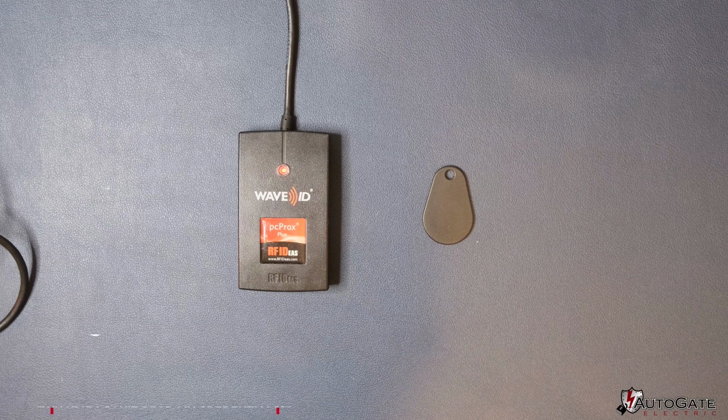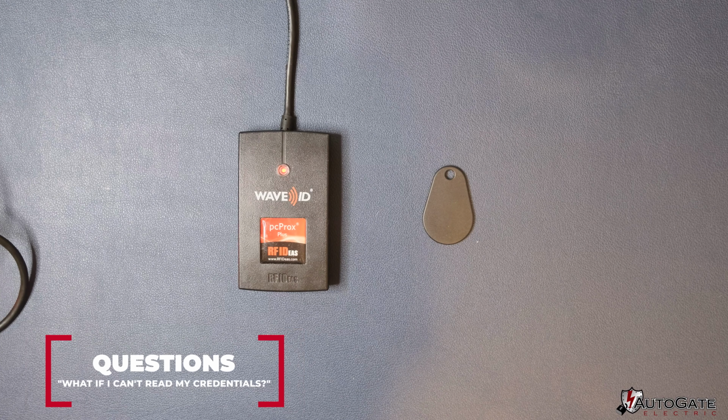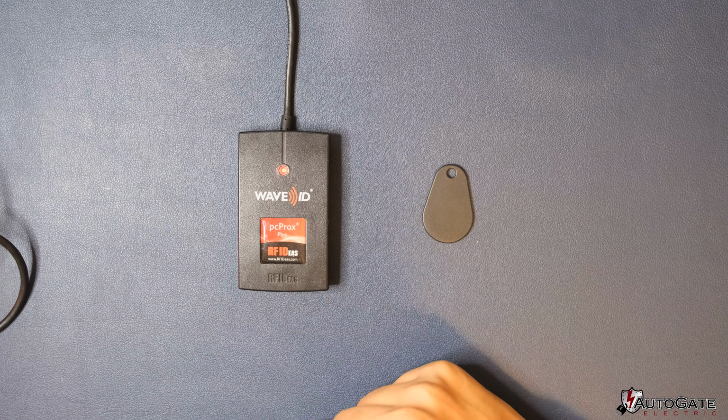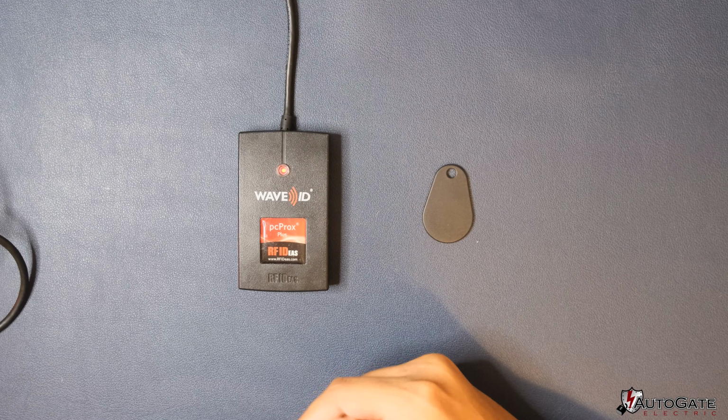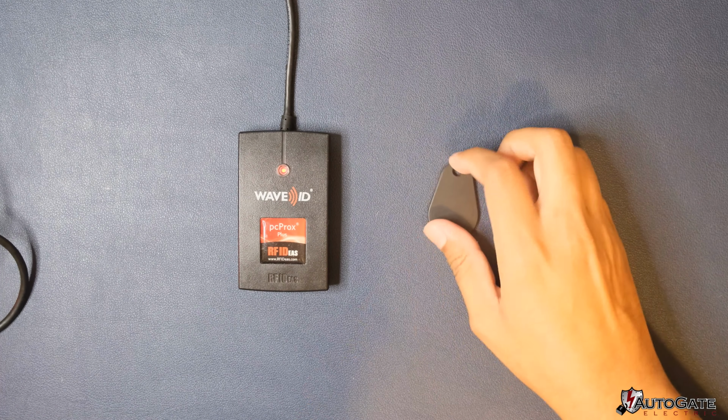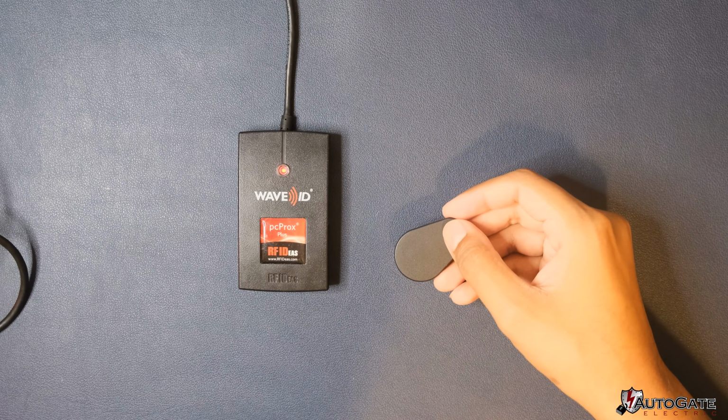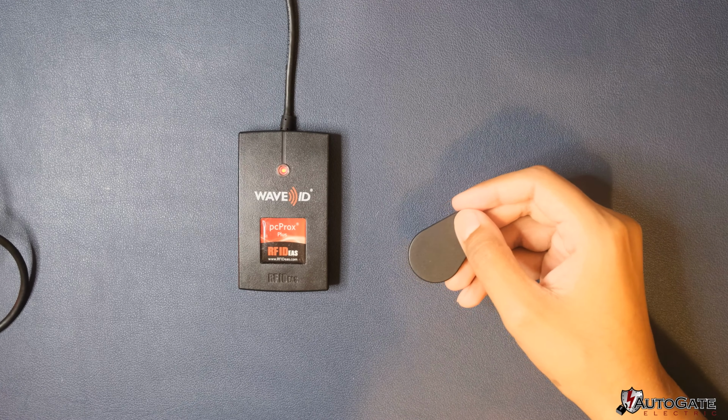Now, here's a question we get a lot. What if I can't read the numbers off my credentials? For some of the technologies, we can provide a special reader that can decode the information for the device. This right here, what you see, is a desktop reader for an RFID key fob. I can plug this into my computer using the USB, open up the Notepad application if you're on Windows, if you're on Mac OS, open up Notes, and when I swipe my key fob over the reader, it will tell me what my facility code and card number is.